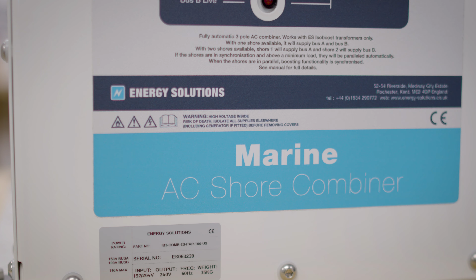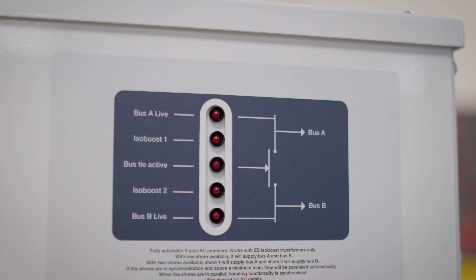But it is often the case that we get a disproportionate amount of load on one cord versus the other. So whilst the AC changeover does a great job in selecting between available supplies, what it can't do is to manage the loads within the two groups of circuits on the boat. We could describe those as bus A and bus B. Commonly, these two bus groups are split into air conditioning on one bus and your other domestic circuits like galley, laundry, audio-visual onto the other bus.